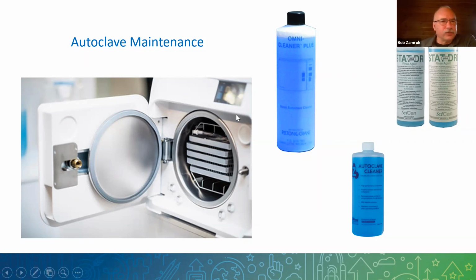Also for autoclaves—we don't have a slide for it, but I'd also bring up your instrument washers. There is maintenance that needs to be done on instrument washers. There are filters on them, and there's cleaner to run through them. It's basically a very high-end dishwasher. If you're familiar with cleaning the filters on a dishwasher at home, you do the same things with your instrument washer.